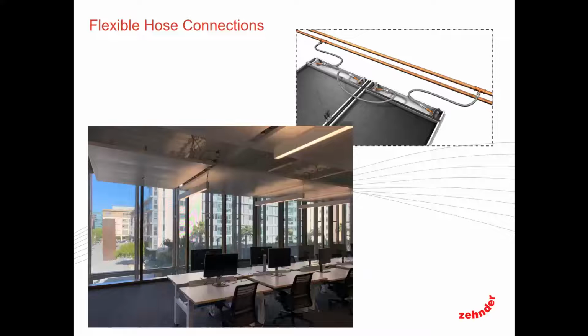All right, I mentioned a little bit earlier, but connections. So panel to panel and supply and return, generally we utilize on these systems flexible hoses. They're oxygen barrier hoses, high rated pressure hoses. You can see your main header here coming off supply and return. There's a valve package here, and then it goes into your circuit and it's returned.